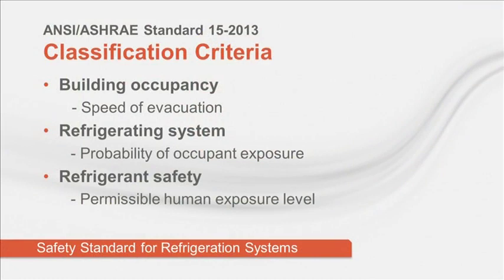Okay, so now that we know when to apply the standard, we need to figure out how to apply the standard. It's important to realize that Standard 15 applies to all sizes and types of refrigeration equipment, from a small window air conditioner that contains a fraction of a pound of refrigerant to a large chiller containing several thousand pounds of refrigerant. To encompass this broad range, Standard 15 defines restrictions for refrigerant use based on three criteria: building occupancy, system type, and refrigerant safety group.